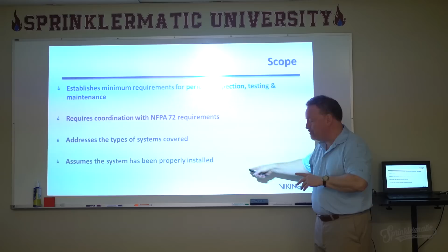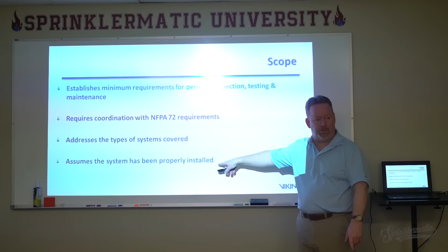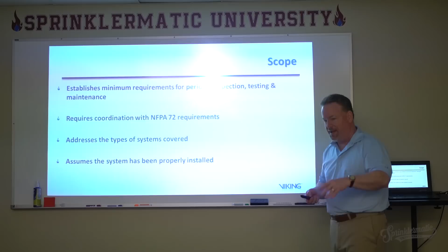Okay, and this is where, when we were drawing the triangle, I said they need to know the standard. The inspection technician needs to know the standard, because they need to know that they don't go trundling out beyond the scope of NFPA 25 if they see something that looks like a design issue. And there are ways to determine that, and we'll get to that in a little bit. So it's not intended to address design deficiencies.